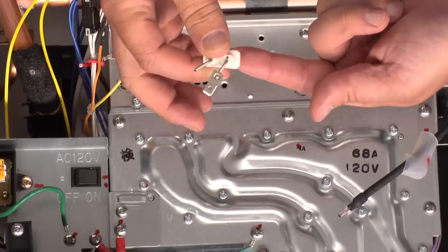It's basically like an oxygen sensor on a car—that's all it's really looking for. But if you have a problem with it seeing the flame, the best thing to do when you inspect this is look at the ceramic, make sure there's no cracks or chips, it's not broken, and then use some fine steel wool and polish it up so it can actually see that flame.